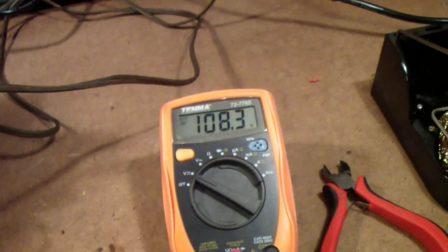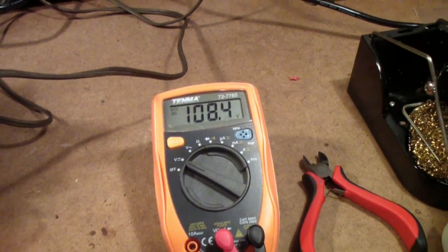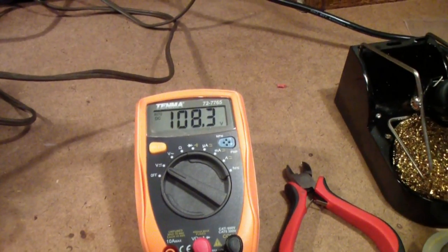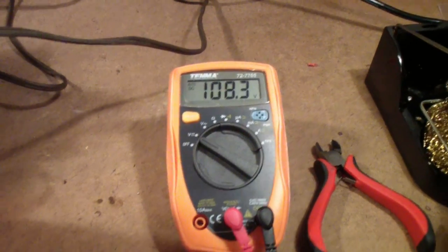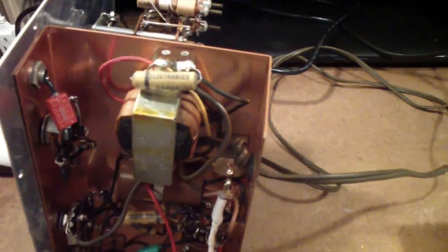and then see how this power supply works. Okay, now the voltage that's supposed to read 110 volts is reading 108.3, which I think is close enough for what I'm looking for here. We probably will have to reset the calibration on this unit anyway. So I think we're good to go.